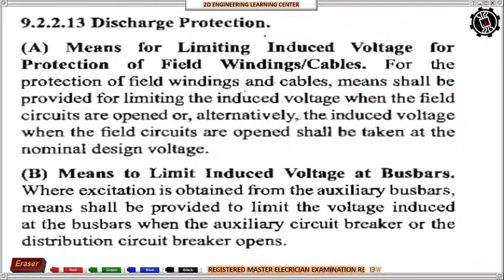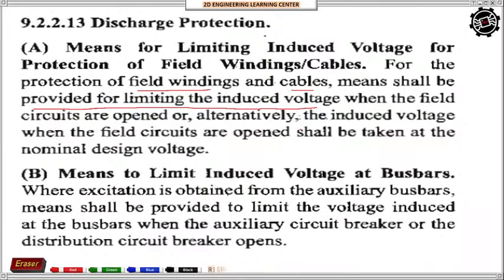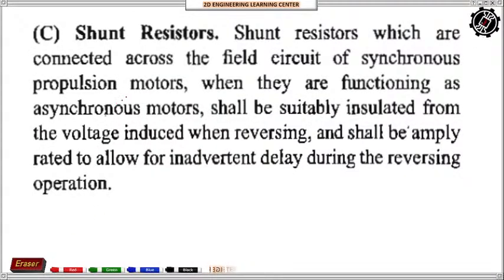So dapat meron tayong proper na discharge protection, no? For the protection of field windings and cables, means shall be provided for limiting the induced voltage. So the induced voltage where the field circuits are open shall be taken at the normal design voltage. So means to limit induced voltage at bus bars, so we must provide proper spacer. Tapos when the auxiliary breaker or the distribution circuit breaker opens, so dapat yung ating induced voltage shall also be extinguished. Yan. So shunt resistor.